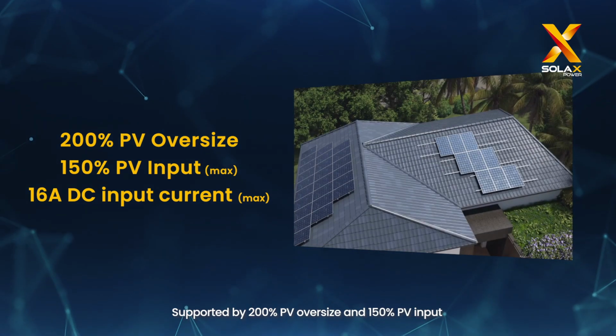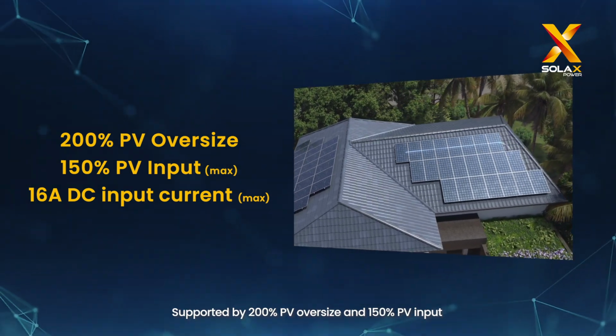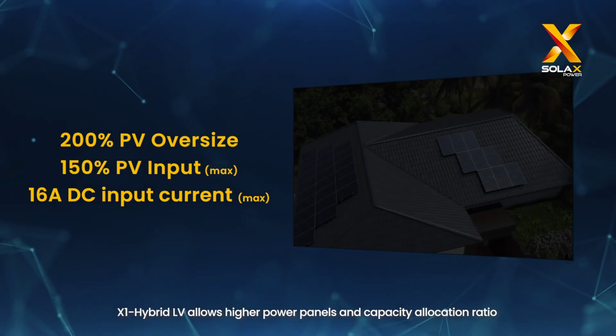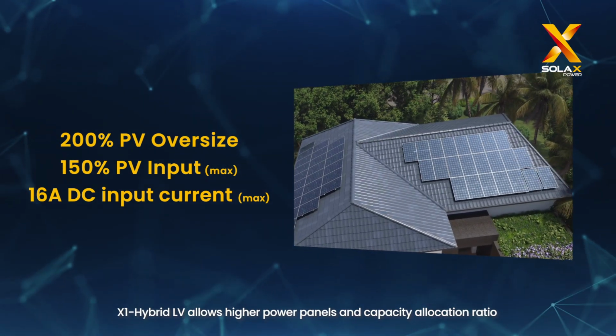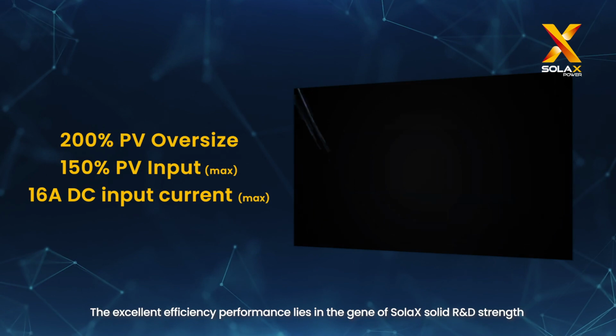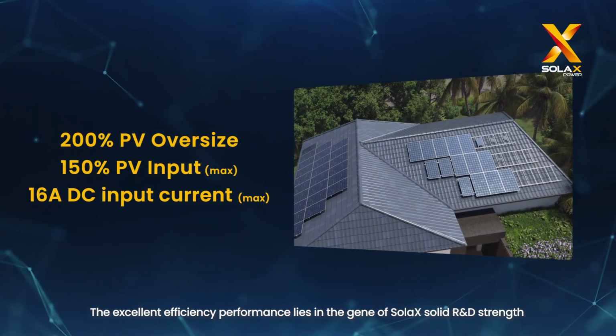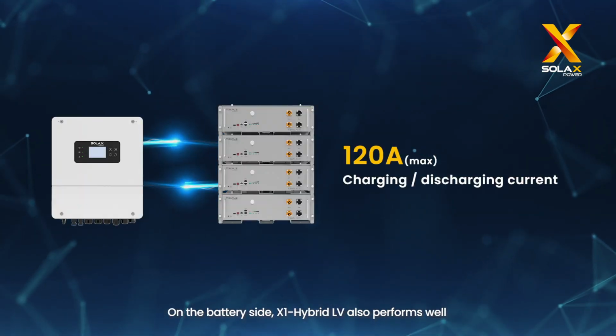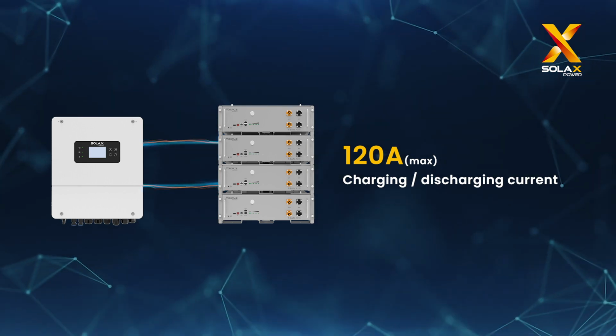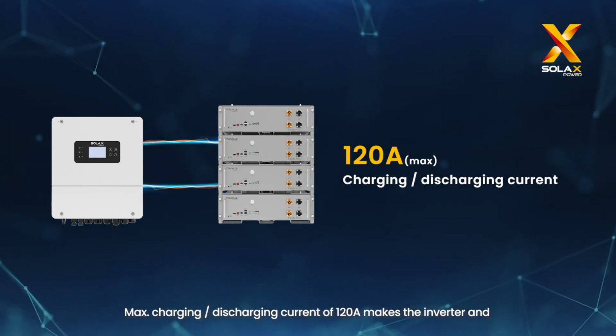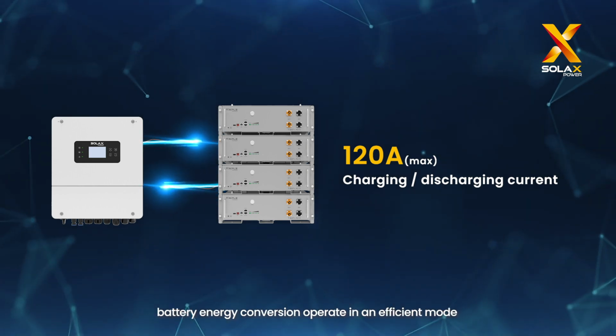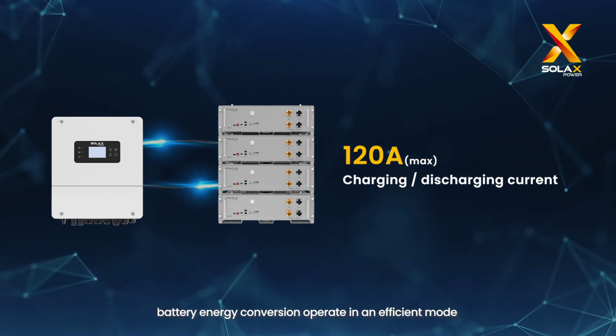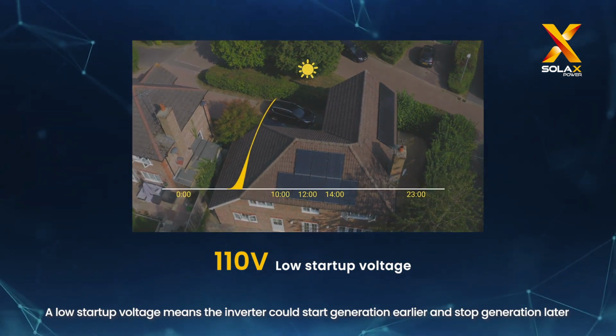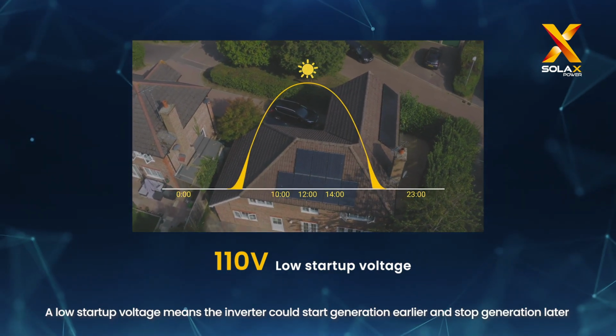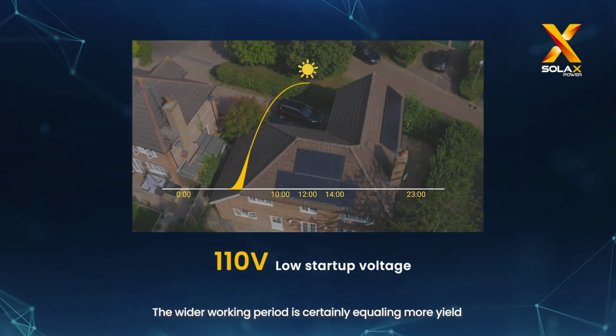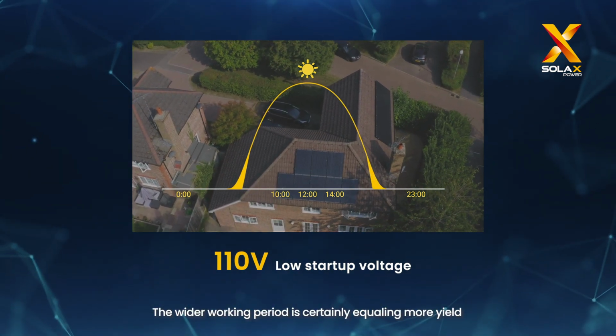Supported by 200% PV oversize and 150% PV input, X1 Hybrid LV allows higher power panels and capacity allocation ratio. The excellent efficiency performance lies in the gene of Sola X solid R&D strength. On the battery side, X1 Hybrid LV also performs well. Max charging/discharging current of 120A makes the inverter and battery energy conversion operate in an efficient mode. A low startup voltage means the inverter could start generation earlier and stop generation later. The wider working period is certainly equaling more yield.